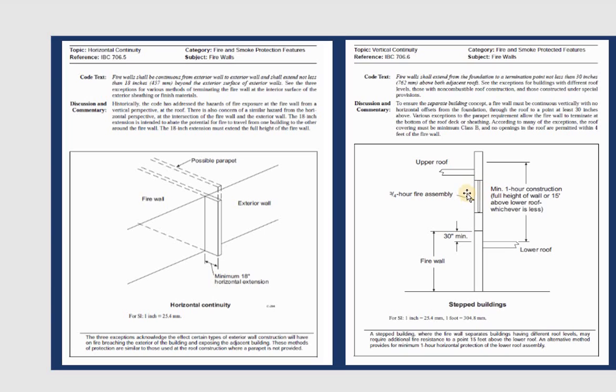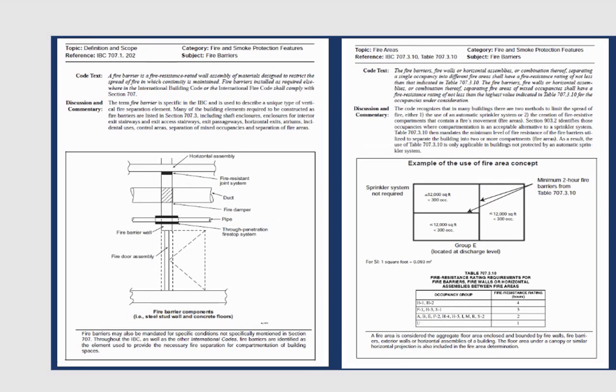For an opening window in that area, you need to use material rated for three-quarter hour fire assembly. For the lower section, if you use the firewall — with the lower roof and the top being the floor of the second level — you go up a minimum of 30 inches. That's where the firewall should be. That's the rule the code shows.